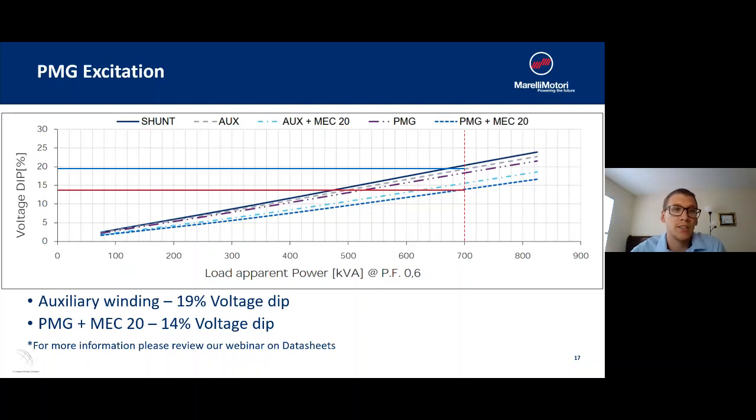Look here at an example of starting a motor with an alternator. Here we have a 700 kVA load. We're going to look at the difference in the AVR with an auxiliary winding versus a PMG with a digital AVR, which is our MEC 20. If we try to start this 700 kVA load with just an auxiliary wound system, we're going to experience a 19% voltage dip. But if we add the PMG with the digital AVR, we're only going to see a 14% voltage dip. For a little bit more information on what you're looking at here, please refer to one of our previous webinars on data sheets.